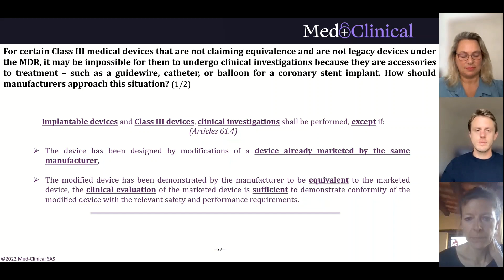Yes, so indeed the MDR provides some exceptions not to perform clinical investigations. If you have an implantable device or a Class 3 device, you should perform a clinical investigation. However, if you have a device that has been designed by modification of a device already marketed by the same manufacturer, so just like an updated version, and this modified device has been demonstrated by the manufacturer to be equivalent to the previous version, and also the clinical evaluation of this marketed device is sufficient to demonstrate the conformity of the modified device with the relevant safety and performance requirements, you don't have to do this.